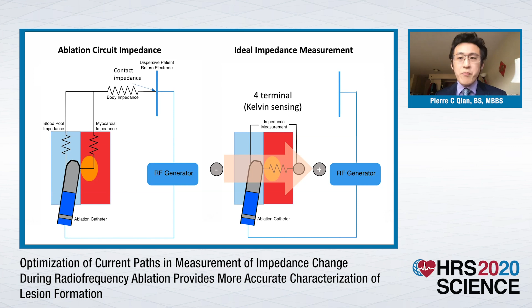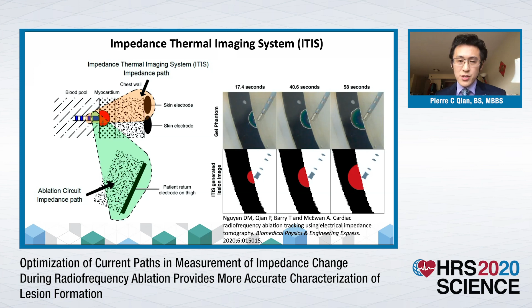Based on this concept, we created an impedance-based imaging system that uses electrodes on the ablation catheter and a set of skin electrodes to optimize the path for impedance measurement through the ablation lesion, and showed in a gel phantom model that this system could visualize heating patterns. We hypothesized in the study that a multi-channel impedance thermal imaging system can be designed and built to interface with standard EP lab equipment, that it is feasible to obtain 4 terminal impedance measurements using skin and intracardiac electrodes during cardiac radiofrequency ablation, and that by optimizing the path of impedance measurement and using a 4 terminal method, the correlation of impedance fall with lesion dimension will significantly improve.